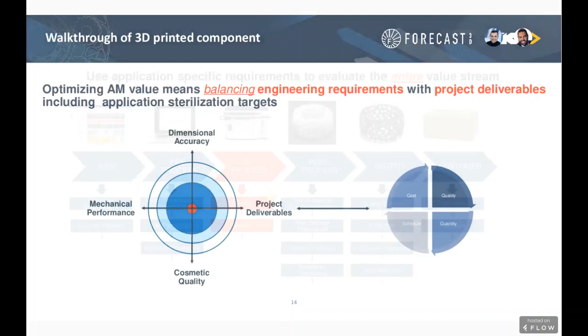So this graph is essentially indicating that some tensile bars were created and printed in a standard fashion, and then tested as a baseline. From there were different test methods or sterilization methods, one being autoclave at 121C, one being autoclave at 134C. Then formaldehyde was a chemical treatment option. It was supposed to be a similar treatment to ethylene oxide. So that data point exists. There's electron beam testing at different power levels, and then gamma radiation.